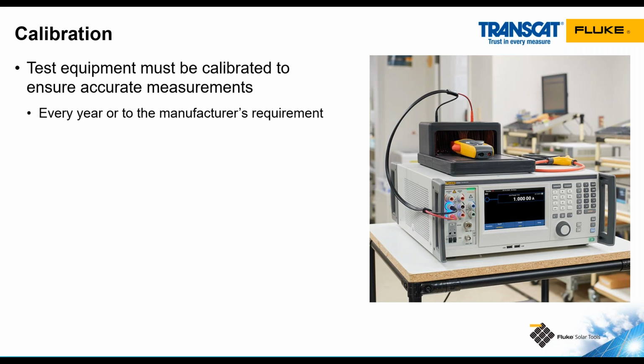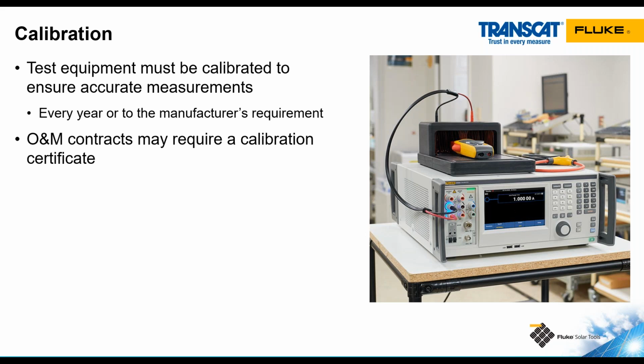Calibration is important with our test tools. Fluke recommends annual calibration for almost all of our products. Read the manufacturer's instructions of your test tool to see what schedule they require calibration. If you're doing third-party operations and maintenance, especially if you're doing testing before the sale of an asset or doing troubleshooting, oftentimes they'll require a certificate of calibration before you start your testing to ensure that you are getting accurate test results.